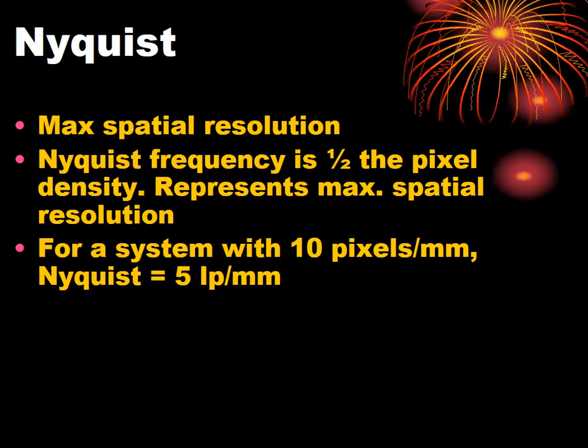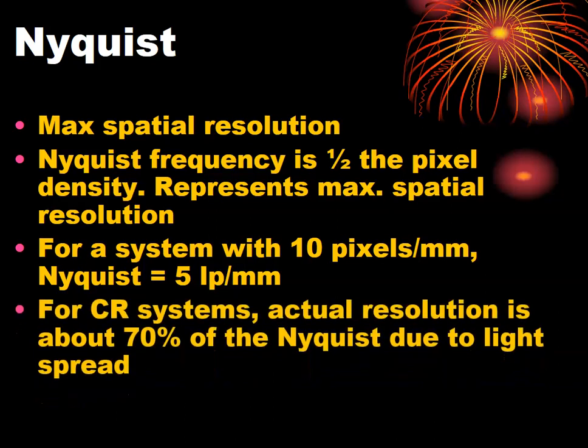The Nyquist theorem states that to achieve a given spatial resolution — say 5 line pairs per millimeter — you need to sample at least twice as many pixels per millimeter, so 10 pixels per millimeter. The Nyquist frequency is one half the pixel density. This indicates the best spatial resolution a given system can theoretically show. For CR systems, actual resolution is only about 70% of the Nyquist value, because the light spread function robs spatial resolution — so a system rated for 5 lp/mm may only deliver about 3.5 lp/mm.